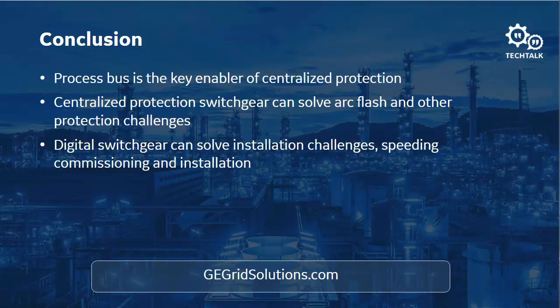What is the cost comparison for a centralized unit compared to having individual 850 feeder protection relays? That's a question that always comes up. It's a cost comparison. As I look at this, you have to buy the MU320, you have to buy the B30s. The hardware costs will be similar between the two, especially if you're comparing an 850 to an MU320.